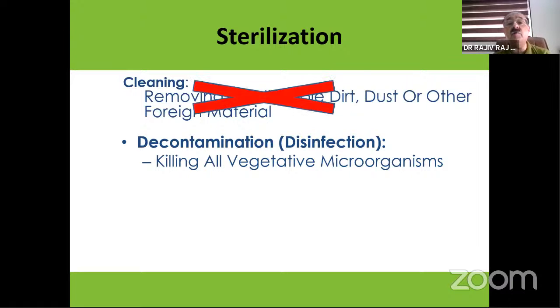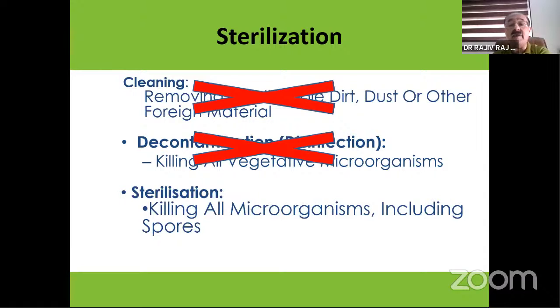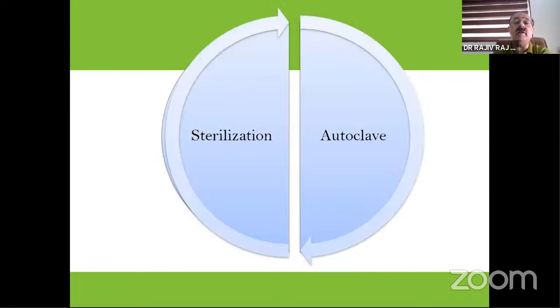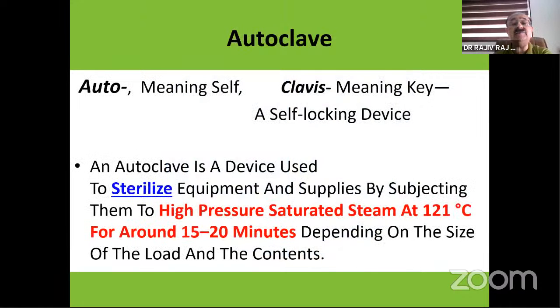So cleaning is the removal of the dust. Killing of vegetative organisms is decontamination, but all microorganisms being killed, including spores, is sterilization. So when we are talking of sterilization, all spores have also to be killed. Now, these are two words very frequently interchanged, sterilization and autoclave. Autoclave basically is the device that is used to sterilize equipment by subjecting the instruments to very high pressure saturated steam at 121 degrees for 15 to 20 minutes. And the amount of time would depend on the size of the load and the contents that we are sterilizing.